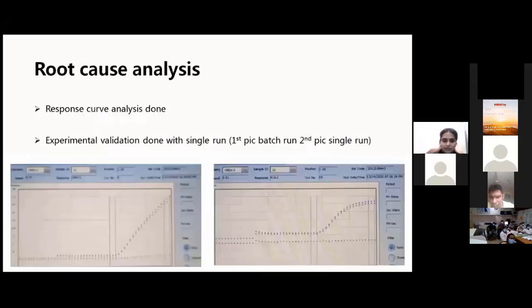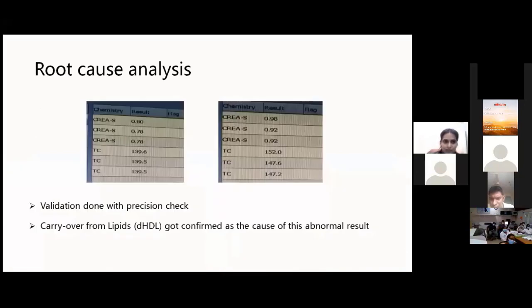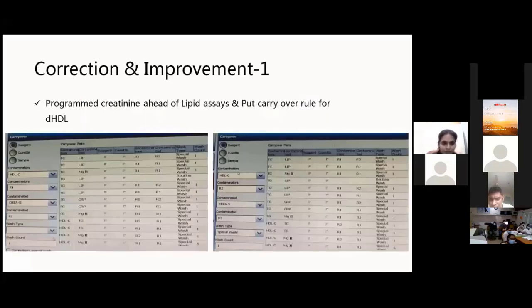Since no other reason was found, we started suspecting a carryover. And then we did a response curve analysis, and this is what we obtained. This is the first run analysis curve, and this is the second one, which is definitely more acceptable. Experimental validation was done with both of these, and a root cause analysis was done. And this is the precision check that we did with the same sample. The precision check was perfectly okay, as you can see. Since all these samples were run following a lipid profile, we expected that there had to be a carryover from the lipids, primarily HDL, because that was the common factor in all these.